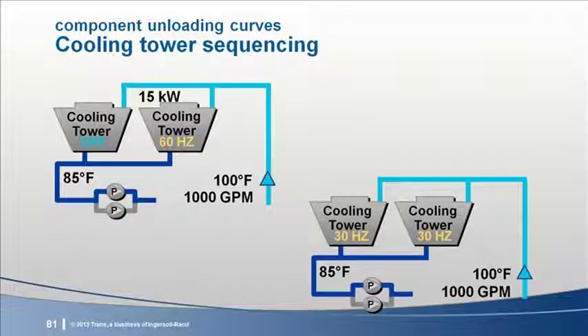This is somewhat of a repeat of the 2006 discussion, but I think it bears examination. What if we changed the cooling tower sequence on the system and ran both cooling tower cells to meet the same operating conditions? If we ran both tower cells, they would each receive half the design water flow. By operating both fans, they would meet the same system operating conditions at approximately 30 Hertz. If you run a tower selection, you'll find it's not exactly 30 Hertz, but for the sake of this illustration, it's close enough to make the point.